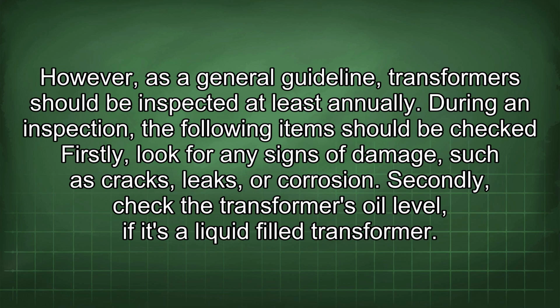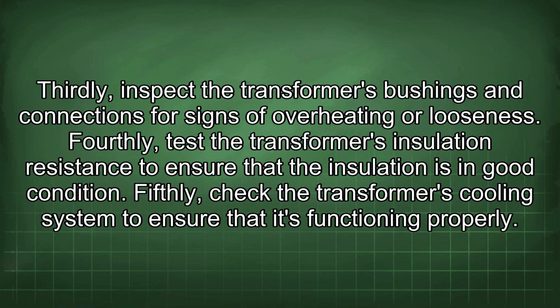During an inspection, the following items should be checked. Firstly, look for any signs of damage, such as cracks, leaks, or corrosion. Secondly, check the transformer's oil level if it's a liquid-filled transformer. Thirdly, inspect the transformer's bushings and connections for signs of overheating or looseness. Fourthly, test the transformer's insulation resistance to ensure that the insulation is in good condition. Fifthly, check the transformer's cooling system to ensure that it's functioning properly.